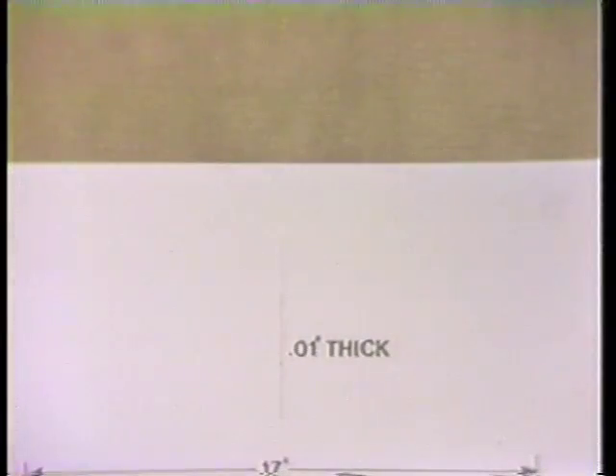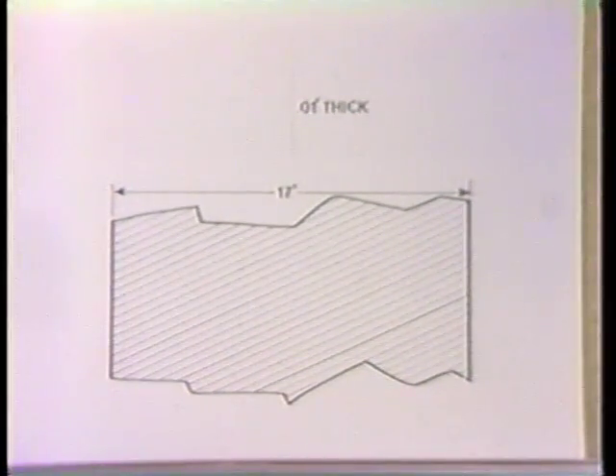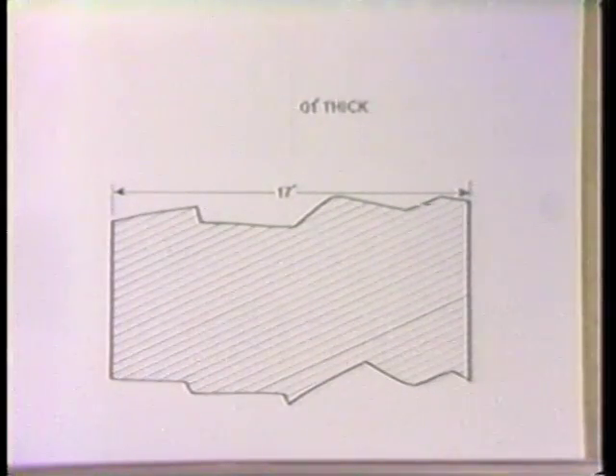Air is one of the best heat insulators in use today. Insulating material merely confines air to minute pockets to restrict its natural convection. The heat conductivity of air is 0.2 compared with 5 for water and 340 for cast iron — iron is 1,700 times as good a heat transfer agent as air. Therefore, a film of air one one-hundredth of an inch thick provides the same barrier to heat transfer as a wall of cast iron 17 inches thick. As little as one-half percent by volume of non-condensable gas in the steam can reduce the heat transfer efficiency by as much as 50 percent.